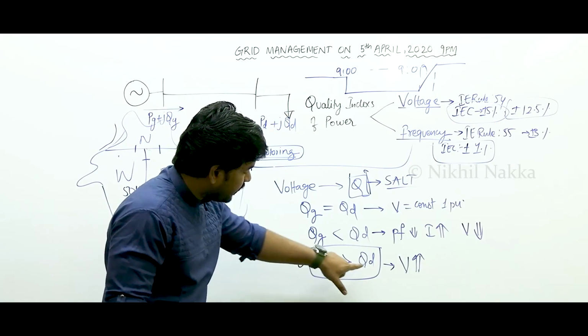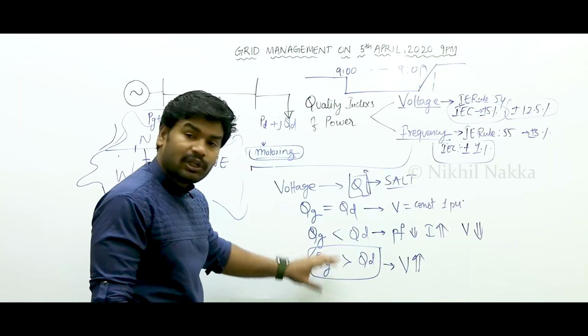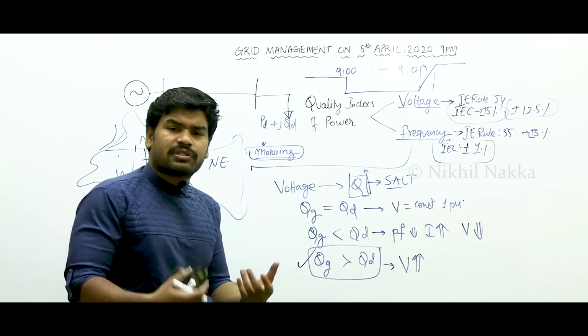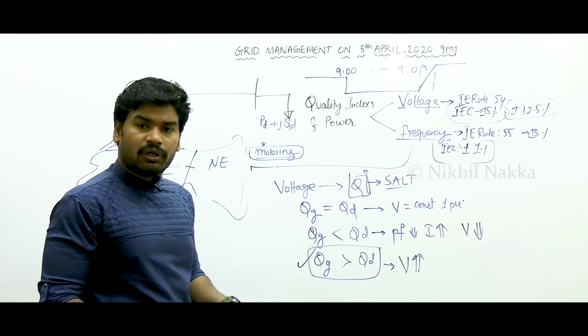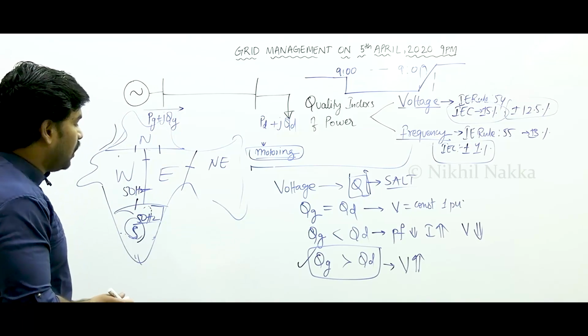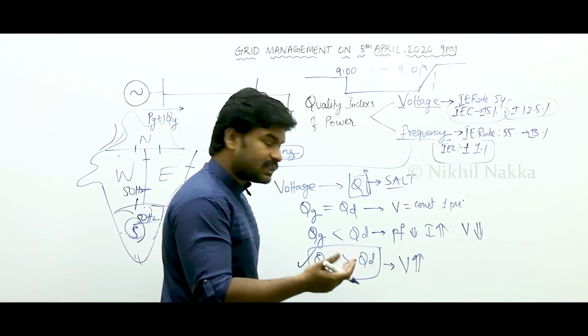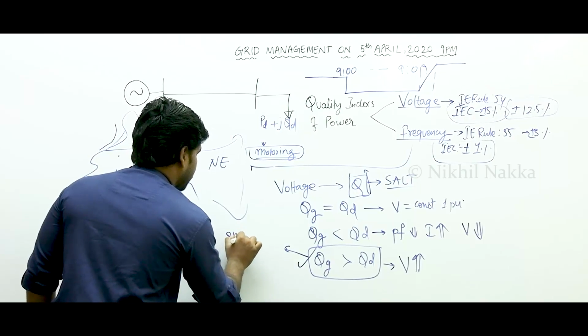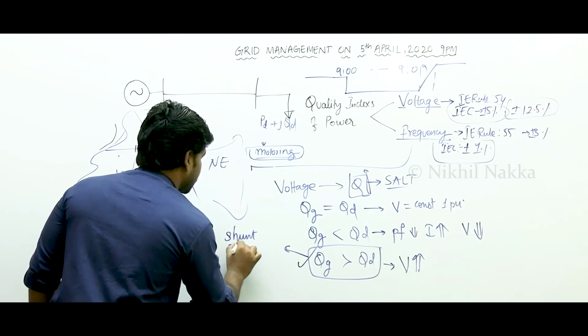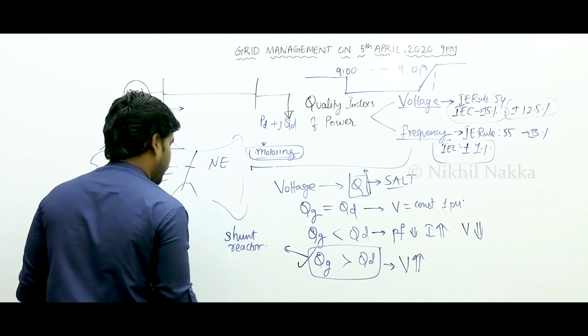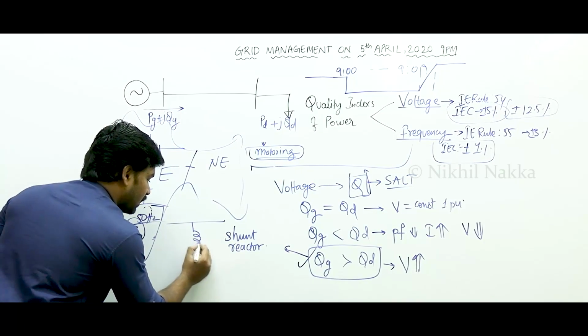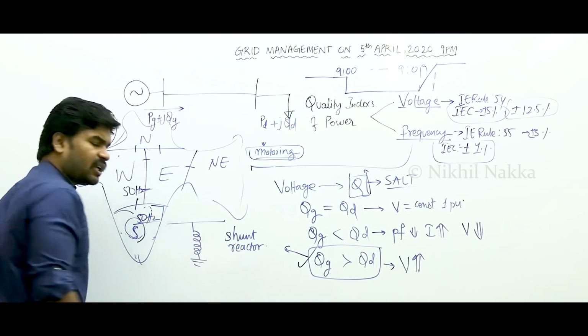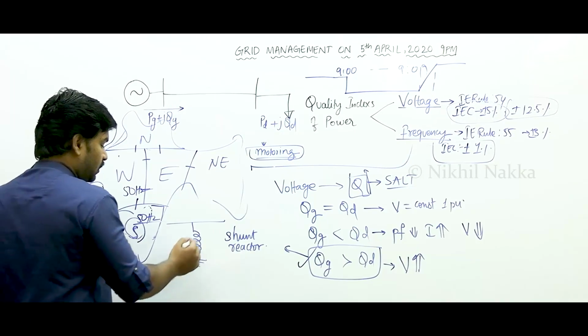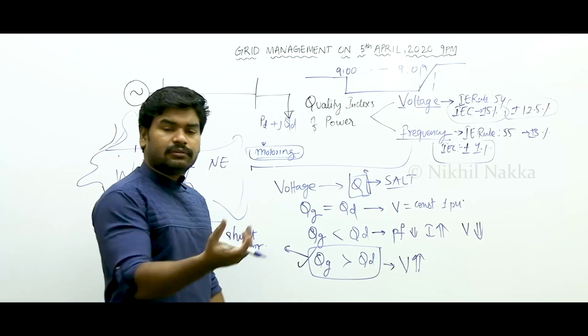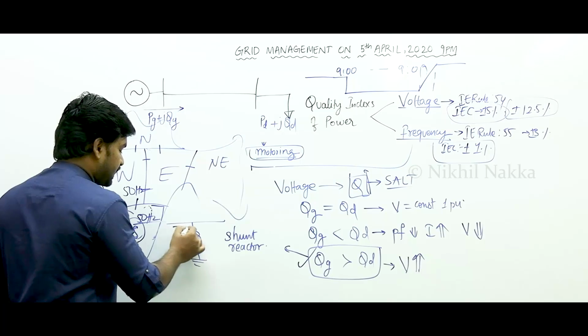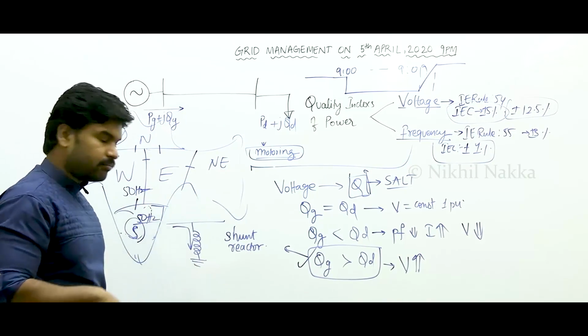So in order to manage it, what should we do? Excessive reactive power generation is there. Try to decrease the reactive power and introduce something that can eat up all the excess. So we introduce shunt reactors. What is a shunt reactor? If this is the transmission line, parallel connect an inductor - this is called a shunt reactor. A reactor is an inductor, it consumes reactive power, so whatever excessive reactive power is there, it eats up everything.